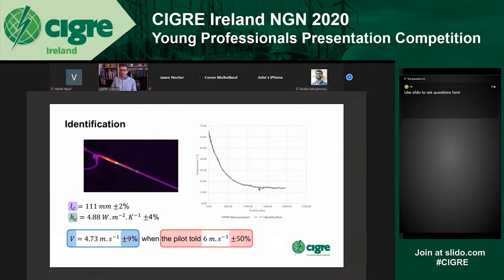With that, I can calculate the convection's heat transfer coefficient HC, it's 4.88. Then I can get access to the wind velocity, more precisely the component of the wind velocity that is effectively cooling down the line, the one I want. Here it's 4.73 meters per second. But what's more important is the uncertainty of that measurement is only 9%.